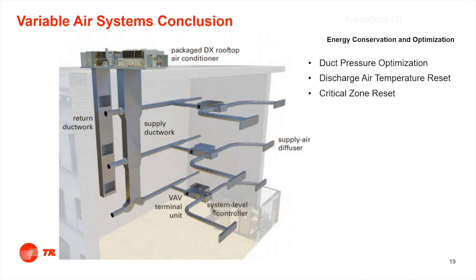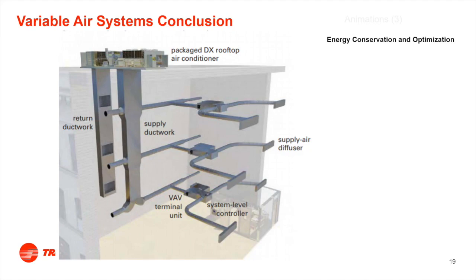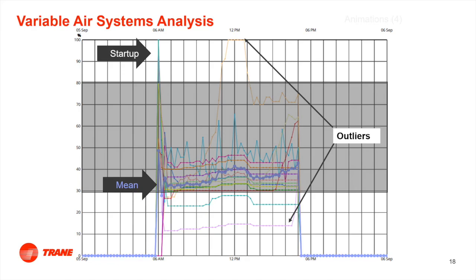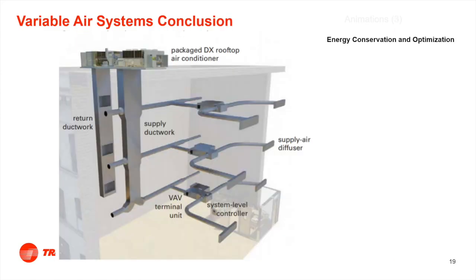Critical zone reset, remember the outlier that I showed you back on this chart? What if I can speed my air handler up to satisfy that one specific box? Would I need to do that? Not necessarily, but I have the power to do that.